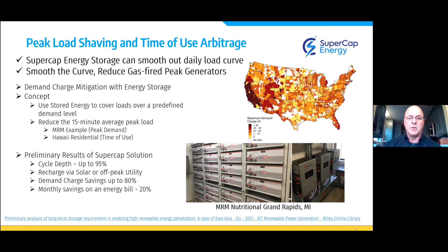Time use mitigation or peak shaving is beneficial for both the customer and the utility. The time use rates in Hawaii are fairly high - daytime rates are down around 12 cents a kilowatt hour because of excess solar, and nighttime evening rates can reach 50 cents a kilowatt hour. That swing is enough to justify moving energy around, and it has a really good return on investment. Demand savings are up to about 80% for this type of peak shaving, and it could cut electric bills by at least 20% for time use.